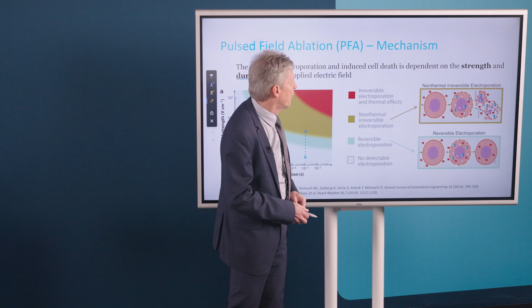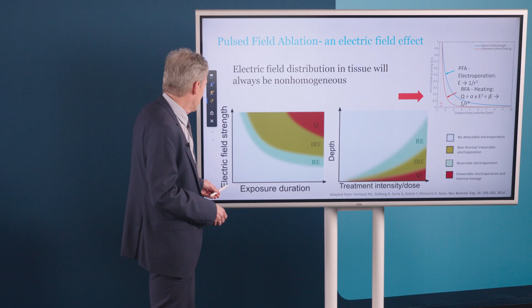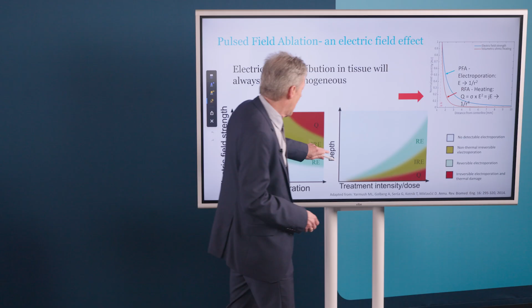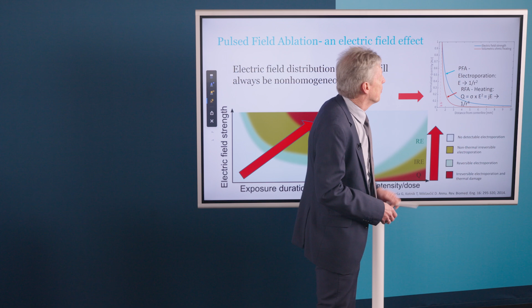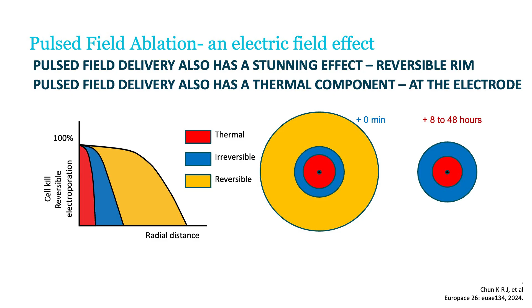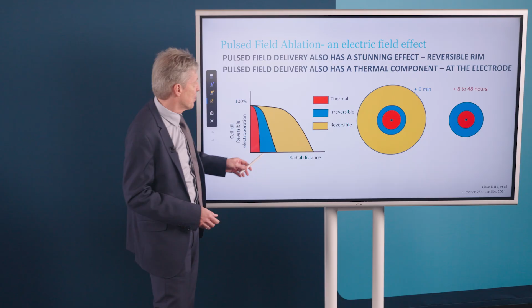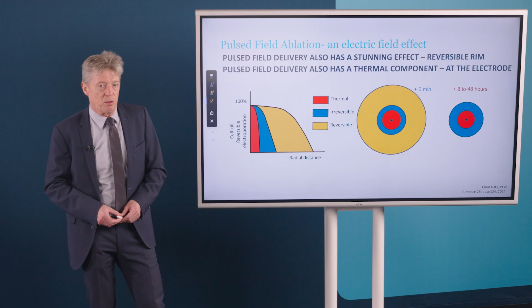The pulsed field ablation and electrical field effect in tissue will always be non-homogeneous. So the effect depends on the electrical field strength, exposure duration, on depth and treatment intensity and the dose, and on the distance of the electrode to the tissue. Pulsed field ablation also has a stunning effect with a reversible rim, as you can see here. And pulsed field delivery also has a thermal component at the electrode, as you can see here.